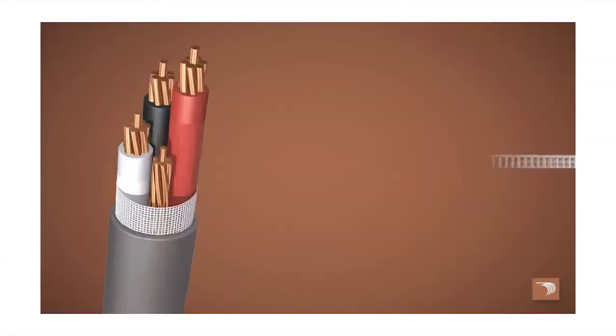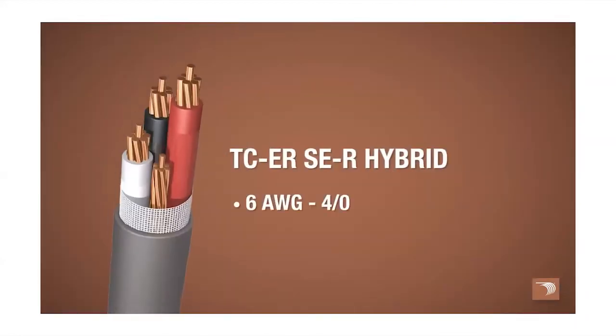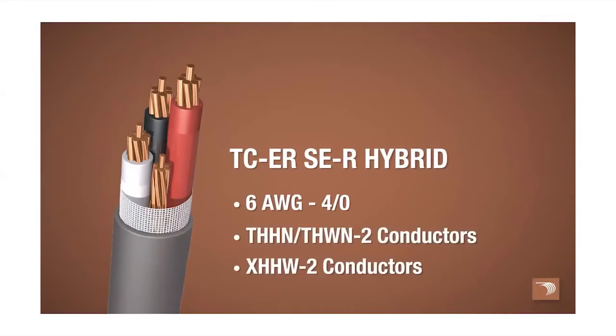Encore WIRE's tray cable is some of the toughest cable on the market, and that same toughness is now featured in our new tray cable SER hybrid cable. Our tray cable SER hybrid cable is suitable for installation in locations where traditional tray cable isn't permitted to be installed, as required by the National Electrical Code. We offer it in sizes 6 gauge through 4/0 with THHN/THWN-2 or XHHW-2 inner conductors.